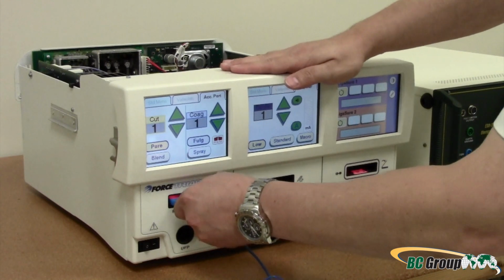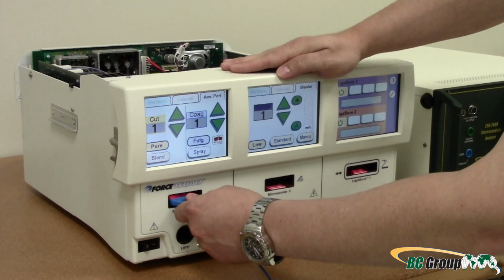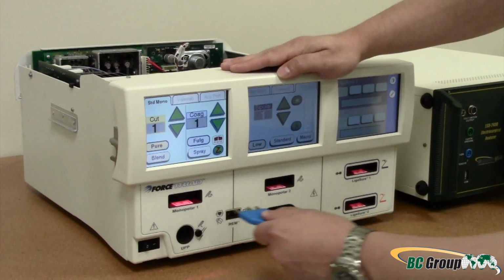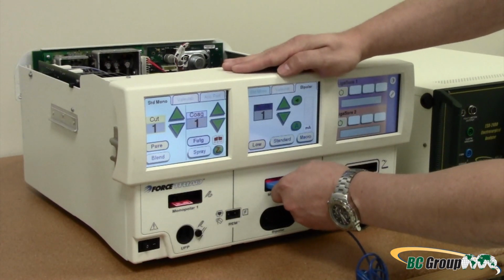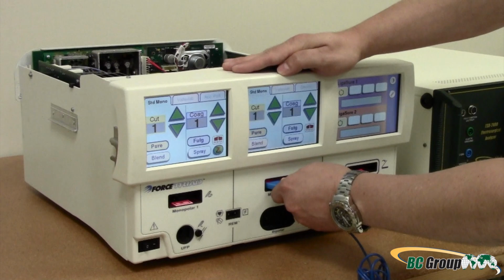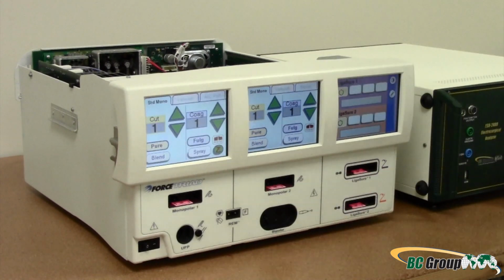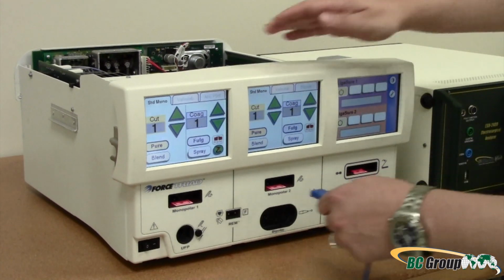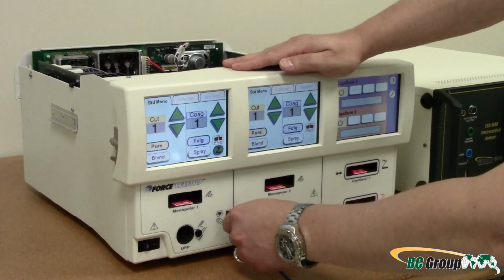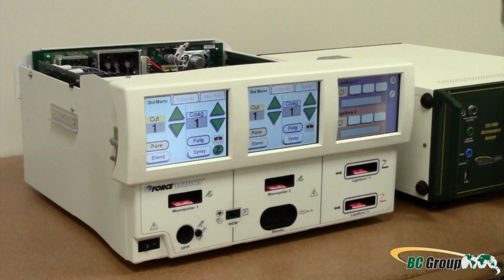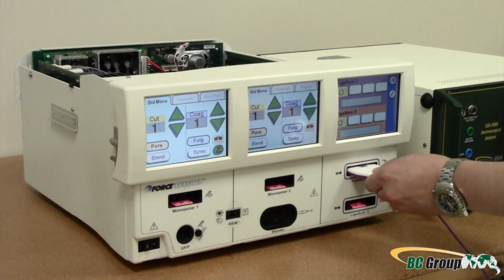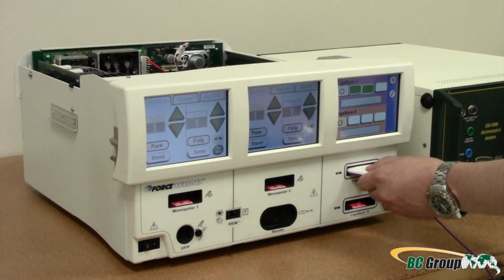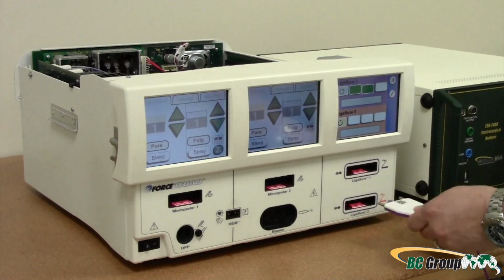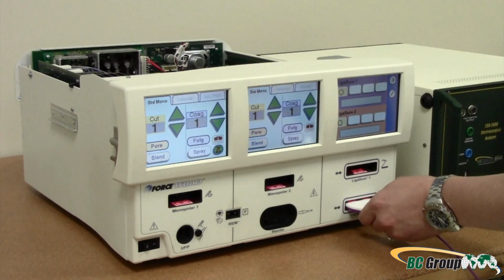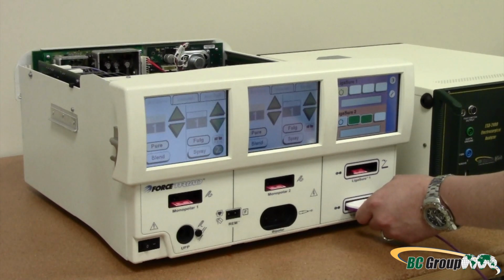Check the monopolar 1 and monopolar 2 ports for obstructions or damage. Insert an electrosurgical pencil into each port to verify a secure fit. Verify that the appropriate tab becomes active for each. Check the patient return electrode receptacle for a broken pin or an obstruction. Check the LigaSure 1 and LigaSure 2 ports for obstructions or damage. Insert the LigaSure instrument into each receptacle to ensure a secure fit. Verify the corresponding control panel becomes active.